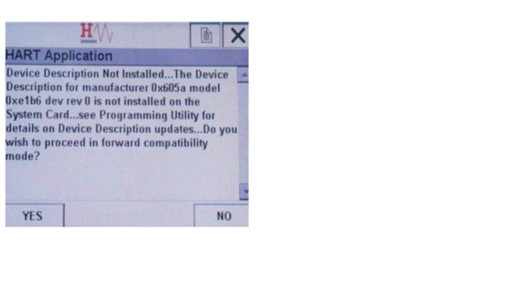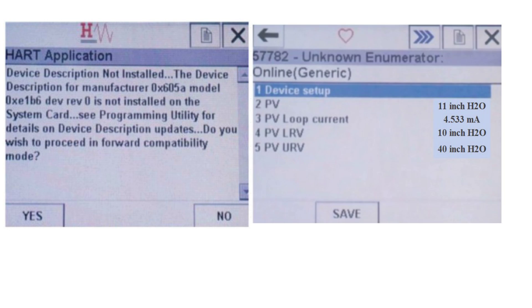If the device descriptor is not installed, the 475 communicator will use HART Universal and common commands to program the radar. As you can see, a message will appear when the device descriptor is not found. Tap the yes button to proceed to the home screen. The home screen displays the primary variable, primary variable loop current, the calibrated lower range value, and the calibrated upper range value.